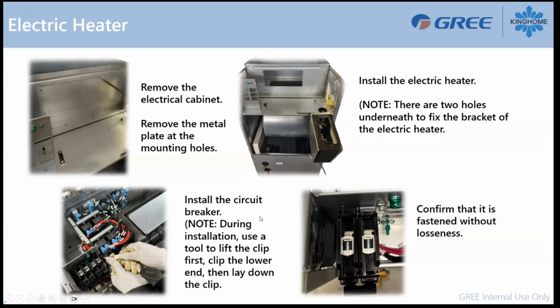When it's time to install those breakers, you will see in the back of the breaker there's a white plastic piece that will help you to clip the breaker in place. So what is suggested here is you can use your screwdriver and just lift up a little bit so you have a hole inside of it. Just lift this plastic clip with your screwdriver, put the breaker in place, and then release it, and you will lock the breaker in place.